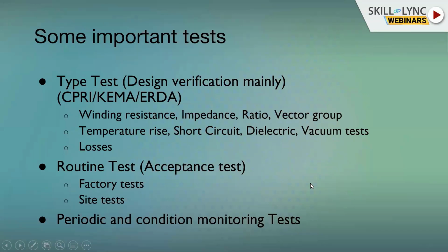And before you decide to use a transformer, it is tested, right? So there are various standards and routine tests as well as type tests. Type test is for design verification. So any new major power transformer has to be type tested. And there are internationally accredited organizations which do this type test in India and overseas. So without a type test, the transformer, whatever you manufacture, is not accepted by a customer.